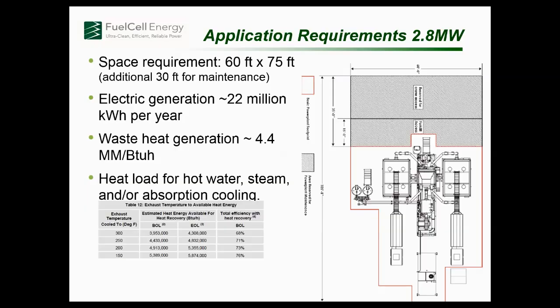So a little bit about the fuel requirements. We need an output of about 55% methane. The CO2 doesn't need to be removed. We can dilute the compositions without derating the fuel cell, so what we do is put in our own fuel cell skid that we build and maintain and manage, so we know what's going into the fuel cell. That makes a huge difference in making sure these things stay up and running.